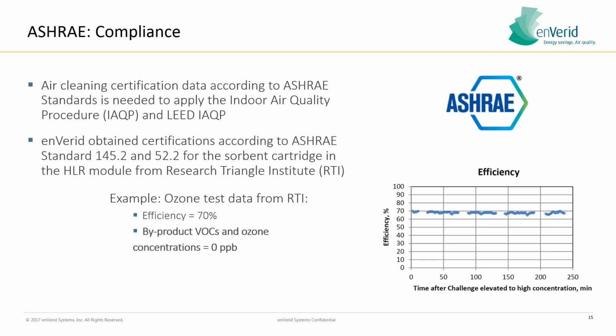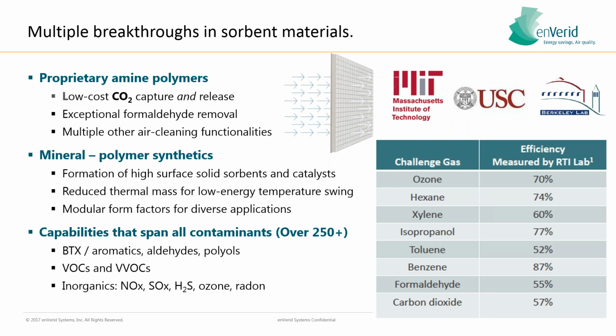This is an example of one of those tests. It's the ASHRAE 145.2 test for gaseous contaminant removal. This is basically for ozone, where you can see that regardless of elevated concentration levels, over time, our efficiency of removing that contaminant remains consistent. So pretty neat. Here's a more lengthy list. It's still a partial list of contaminants that we remove in our efficiencies. And you can see at the top of the screen there, the HLR's cartridges. That's essentially a very robust filter filled with a sorbent. It's about an inch thick. It's 2 feet wide by 2 feet tall. And there's 12 of those per unit. And basically these are what are removing the contaminants of concern from the air that we're scrubbing from the return air.